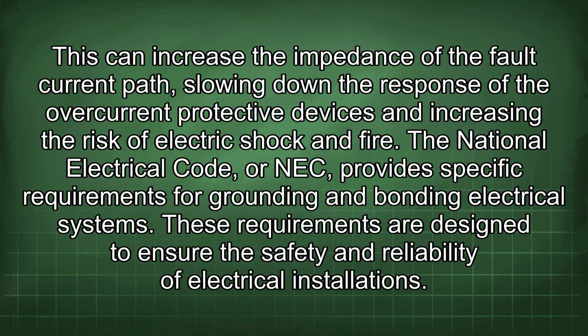This can increase the impedance of the fault current path, slowing down the response of the overcurrent protective devices and increasing the risk of electric shock and fire. The National Electrical Code, or NEC, provides specific requirements for grounding and bonding electrical systems. These requirements are designed to ensure the safety and reliability of electrical installations.